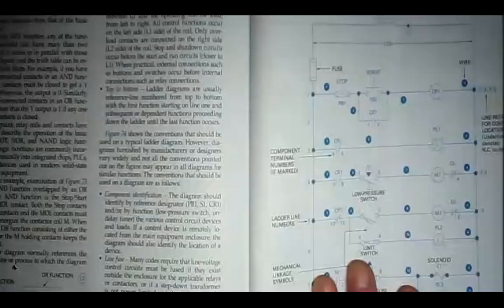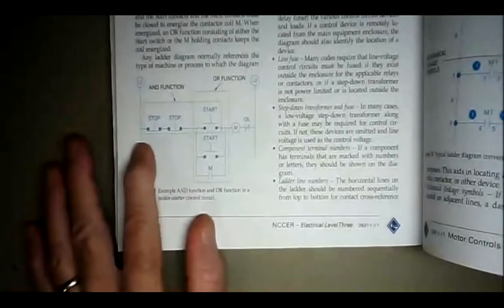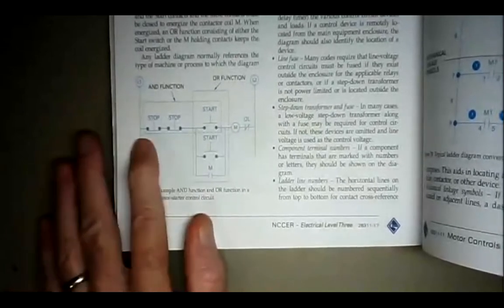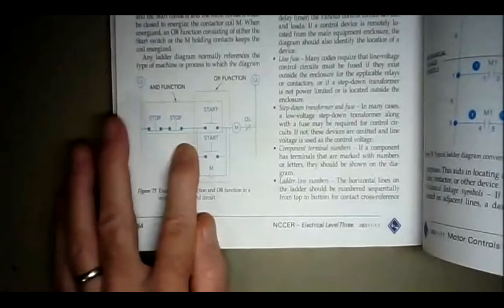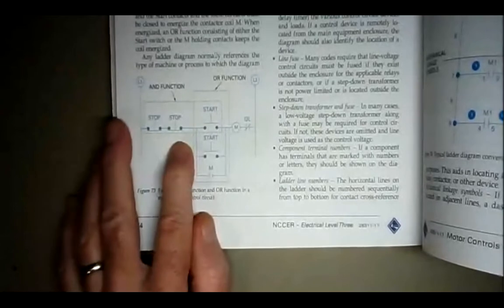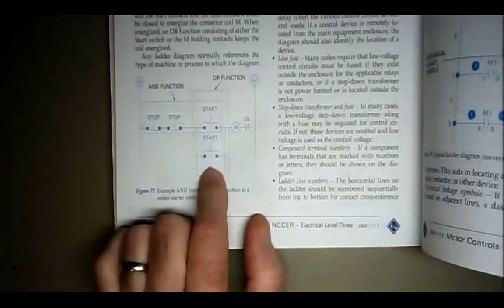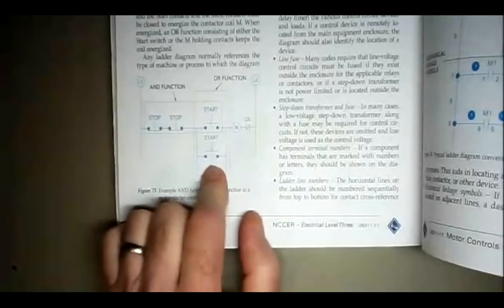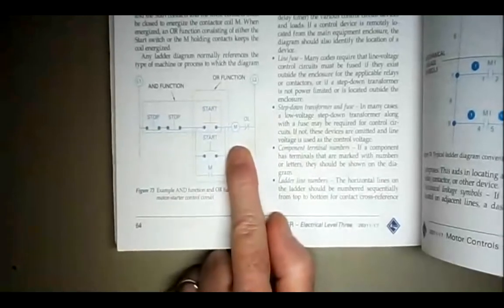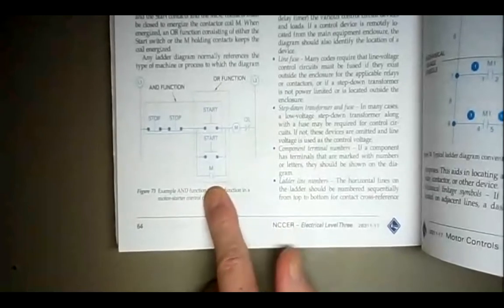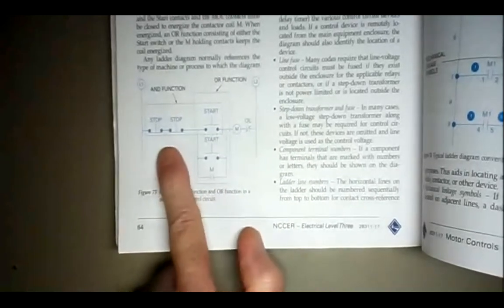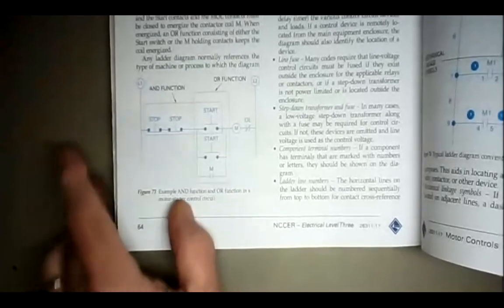Okay. I think we're coming down to the end of it here. Here are some functions. Here they're talking about these two stops. If you have more than one stop, they have to be in series because either one of them that you push, you want it to stop the current or the voltage. So you put them in series. So your stops are in series, your starts are in parallel. So that either one of these normally open start buttons, you can push either one and get your output and get the M contactor to energize. So they're saying that this is an AND function and this is an OR function.